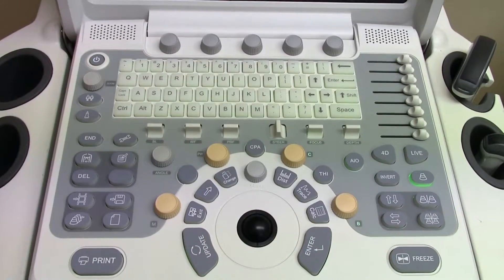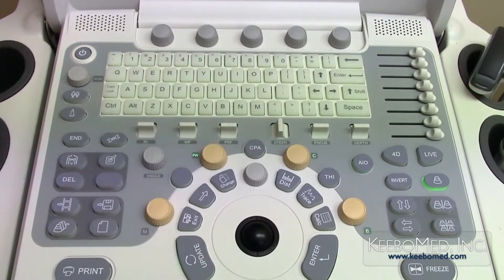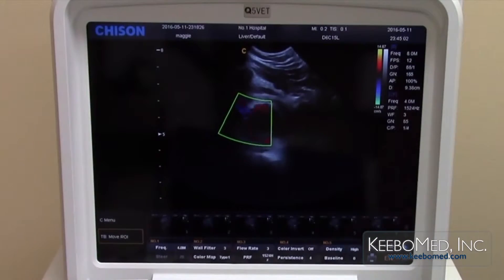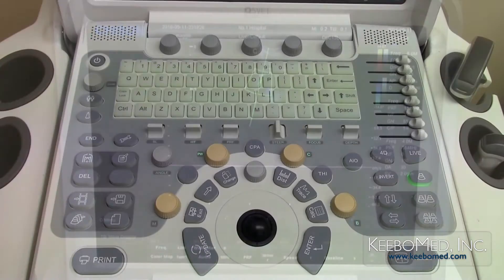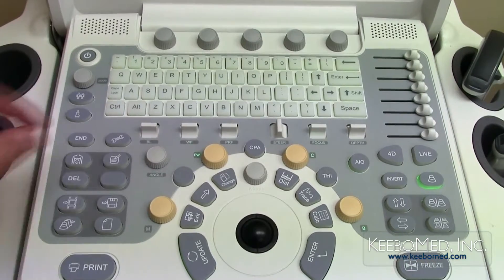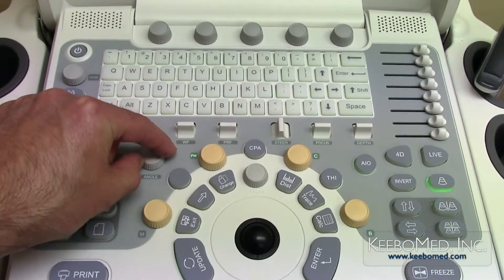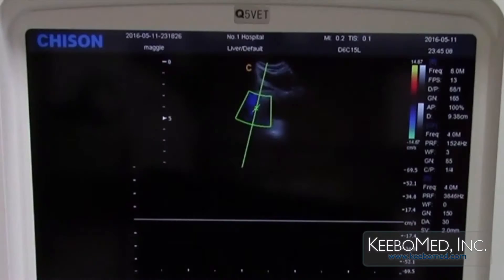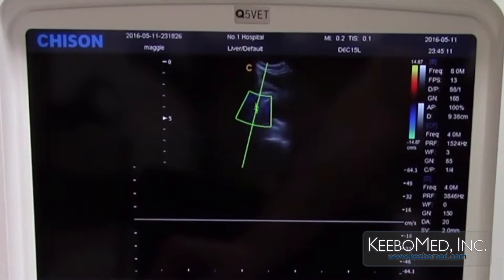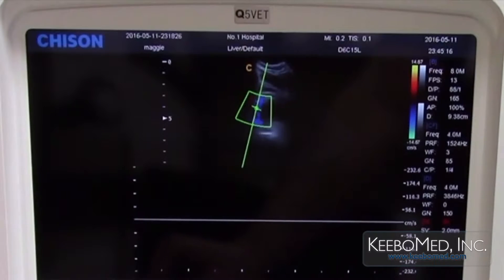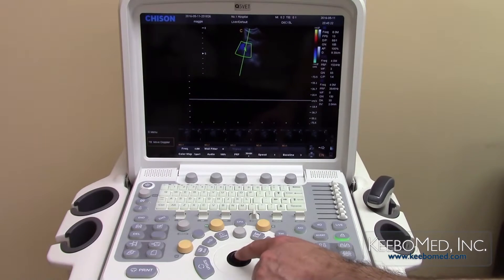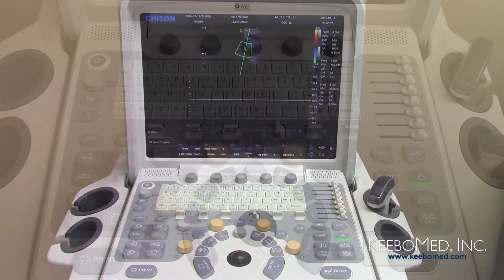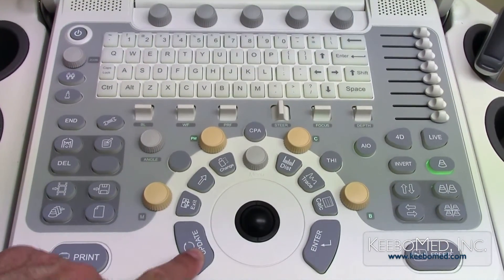To select Pulsed Wave Doppler mode, press the PW button. The angle can be adjusted up to 60 degrees by rotating the angle button; the angle must be kept at 60 degrees or under. The parameters are shown on the right side of the screen. Moving the trackball will allow the line to be moved into the middle of the blood flow, then press the update key to see the spectrum.